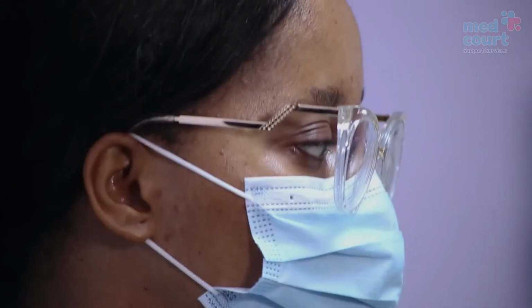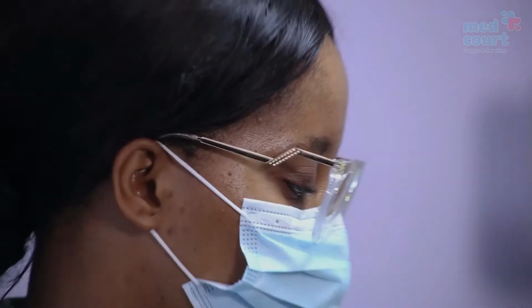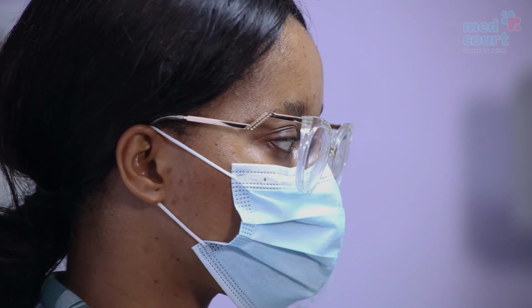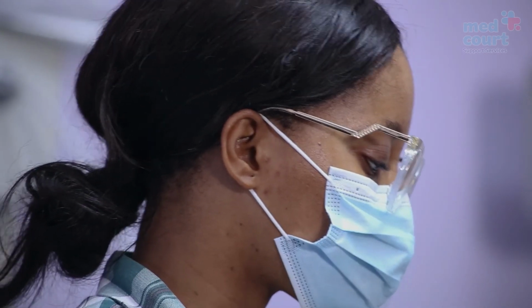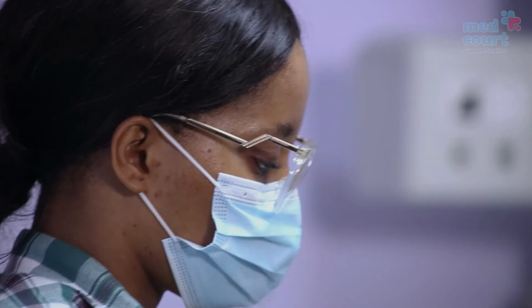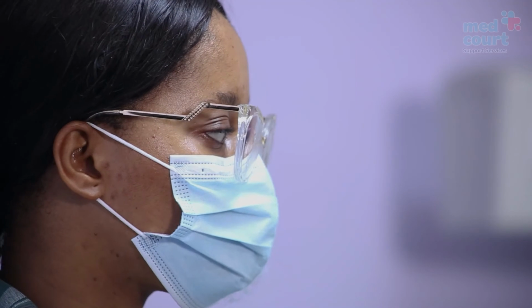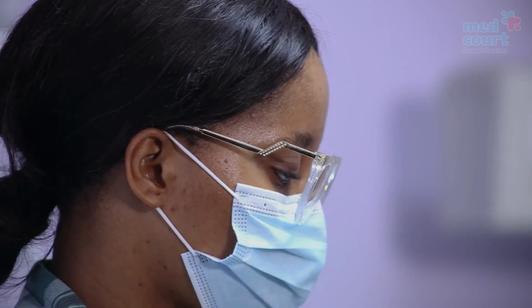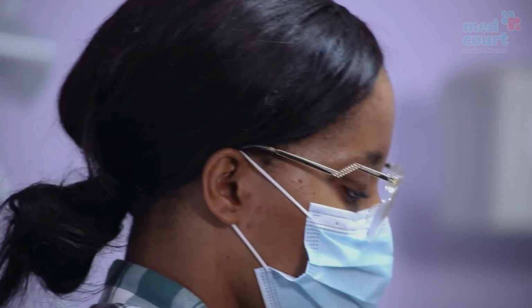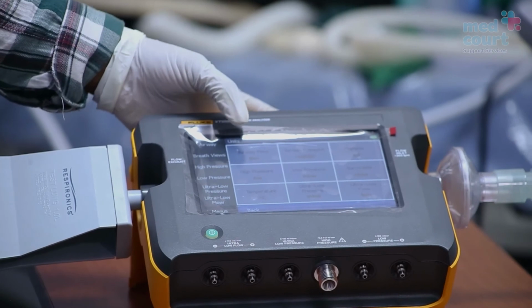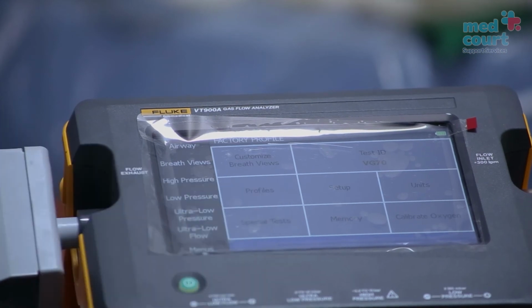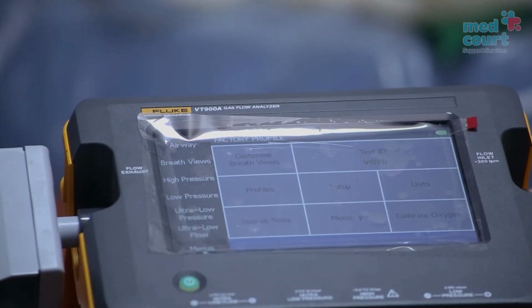Before you start ventilating, ensure that the units on the VT900A match the units on the ventilator. To get to this section, click Menus, Units, and confirm that the volume unit matches the units on the ventilator. We will be using milliliters. Click on milliliters and click OK. Also go over all other units and confirm. Go back to the main menu and start ventilating. So we'll start ventilating now.